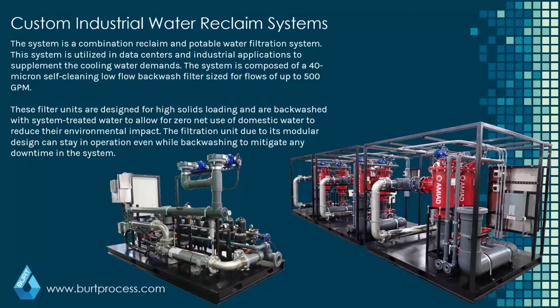So it's in a very similar vein to a rainwater reclamation system, but you're using a similar technology while also taking into account the differences of now being at ground level, with different solids constituents in the system. So I have a basic concept of filtration and disinfection, and now it's looking at the different solids loading, the different filter technologies that go into that type of system, and also the much higher flow rate involved in doing that.